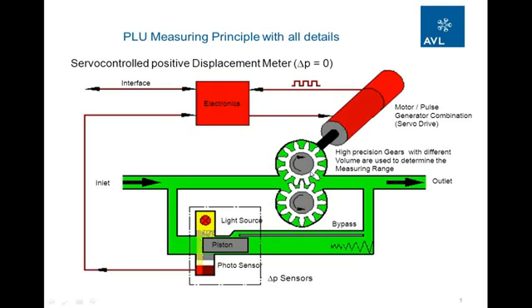And that means we have nearly no wearing effect here in these bearings. And that is the first reason. The second reason is we are using electronic components, and electronic components will change with the lifetime. But here in this case, if the capacity of this light source changes from 100 to 80%, it will directly be compensated by this piston. That means the piston goes to a new working position and the same light can come to the photosensor. That means this complete delta P sensing part is 0-point stable. And that is the second reason for the long-term stability.